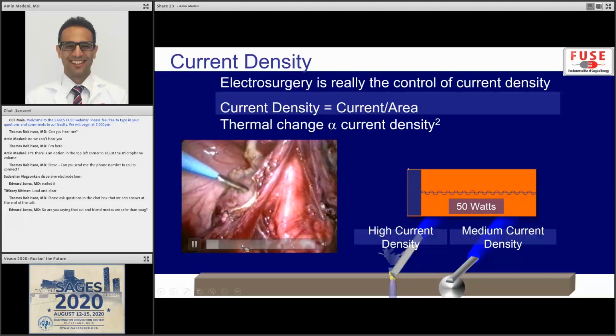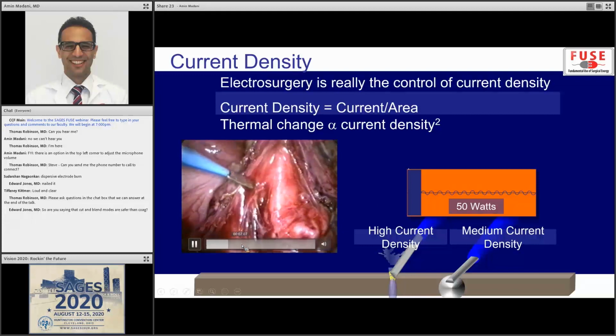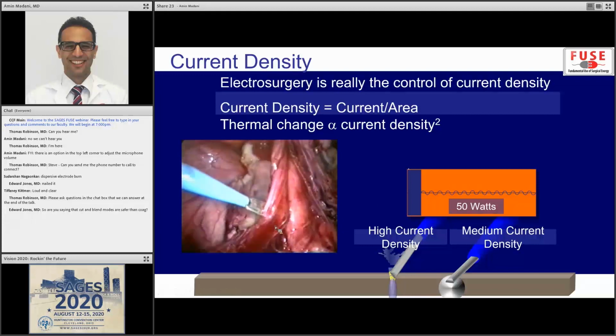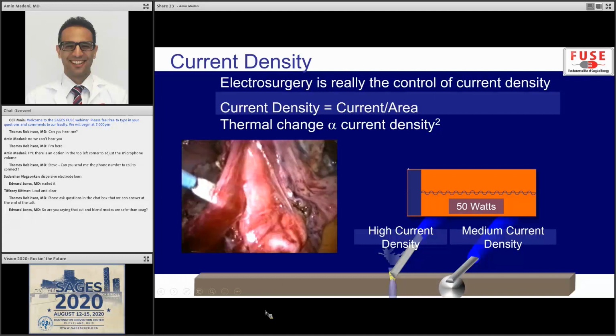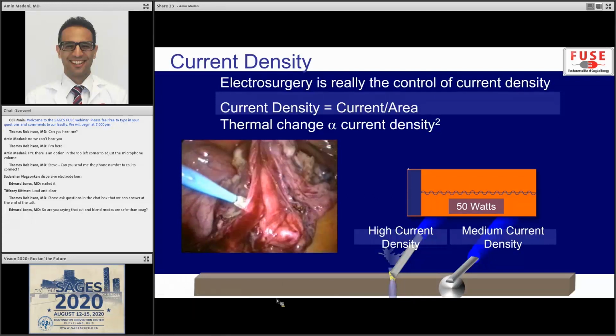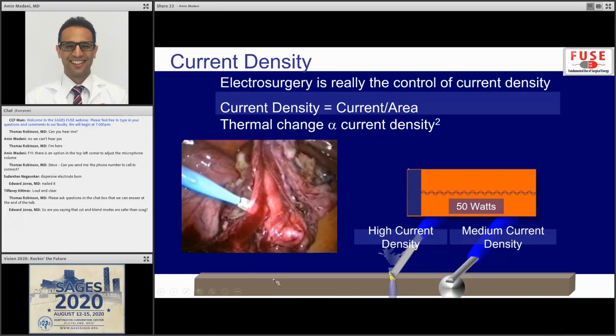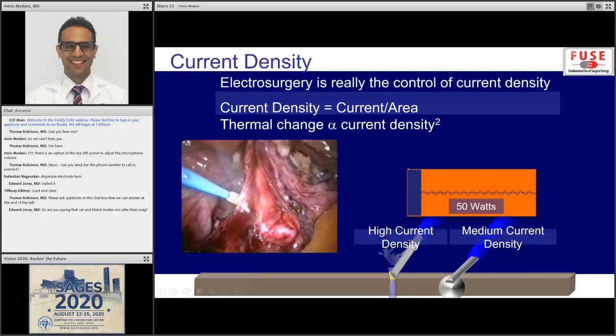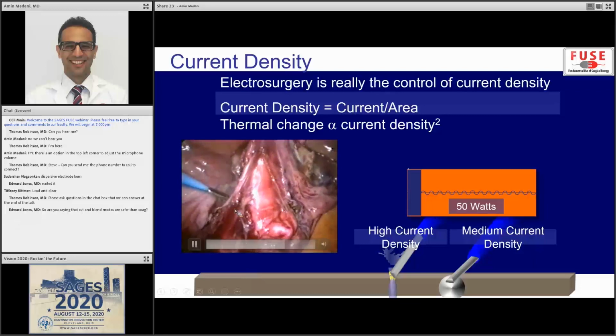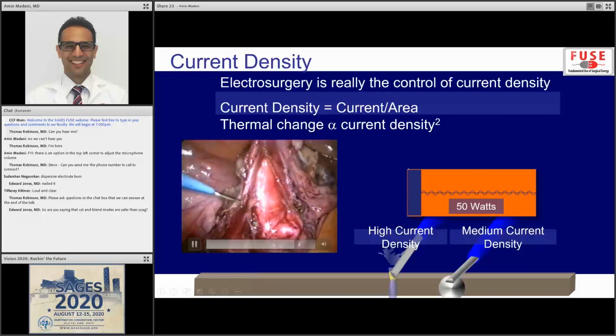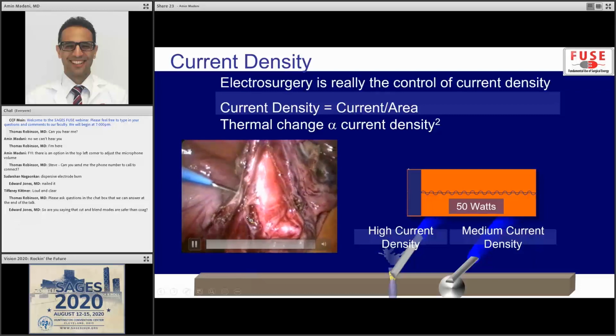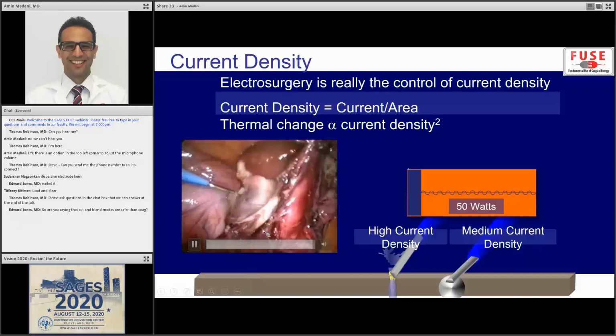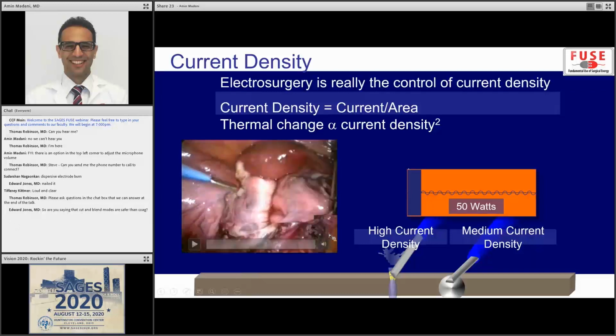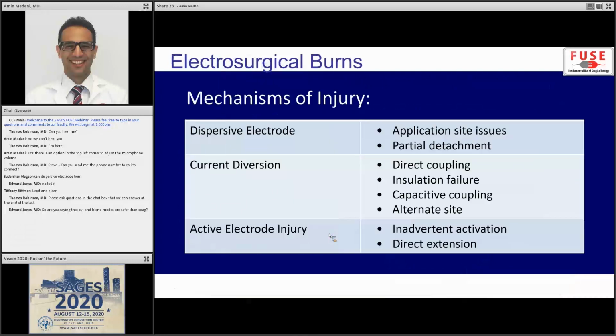In this video, you can see the surgeon is going to use the flat part. That's a large surface area, low current density, and it's enough to raise the temperature to the 60 to 90 degree range for desiccation and coagulation. But when you start using the tip, the current density is a lot higher, so you get more vaporization instead. You don't have to necessarily increase the watts on the ESU to get the maximum thermal effect.